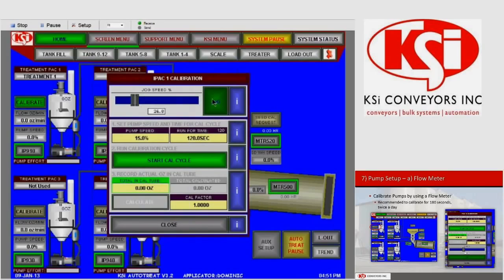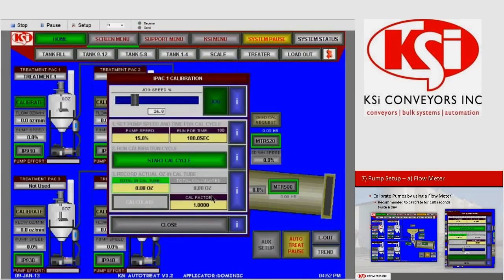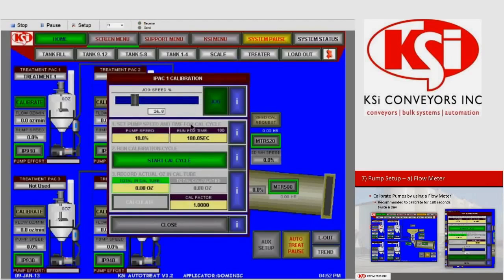Once we have it on 0, we open up our calibrate window by pressing the calibrate button. We'll notice that when we're in here, we also have the option of doing a jog. If we press and hold this jog button, our pump is going to run again. Okay, once we're in here, the first step in running a calibration process is setting the pump speed and the run for time. The pump speed needs to be low enough so that we do not overfill our cal tube, and the run for time we recommend 180 seconds. And this is a high rate pump, and so we want to probably set our pump speed at 10% so that we don't overfill it. So our pump is going to run for 180 seconds at 10%.